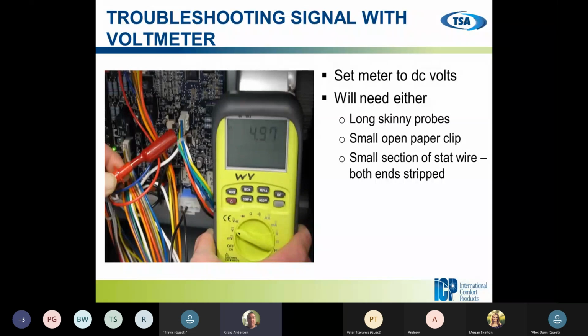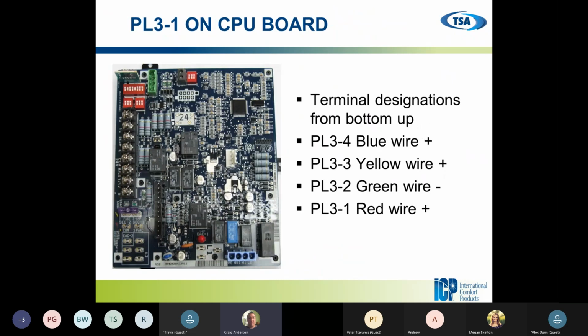When you're pushing the plugs back into the boards or the motors, after the plug is secured, take the wires and push the wires in as well. We want to make sure we have no loose connection. It just could cause a whole different problem on the job site. So if we're using our voltmeter terminal designations from the bottom up, we're looking at a blue, a yellow, a green, and our red wire. So one's going to be our feed in, one's going to be our feed out, one's going to be our ground, one's going to be our neutral, and we'll go through this.